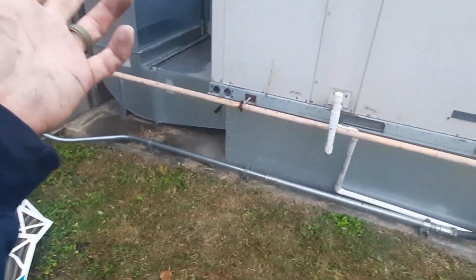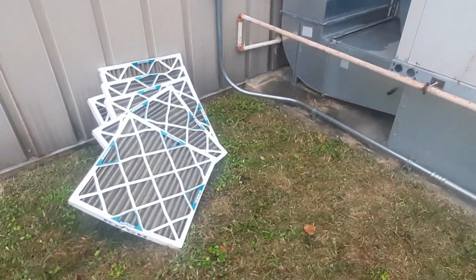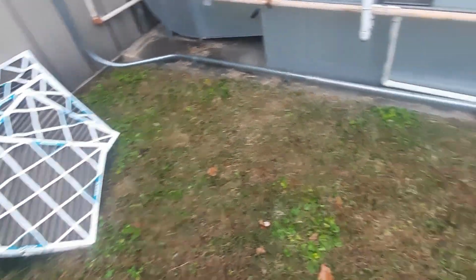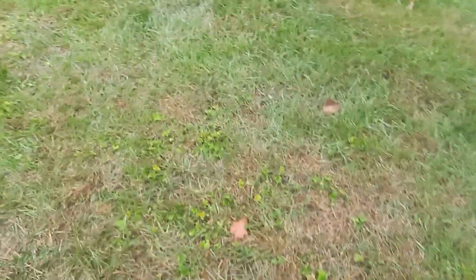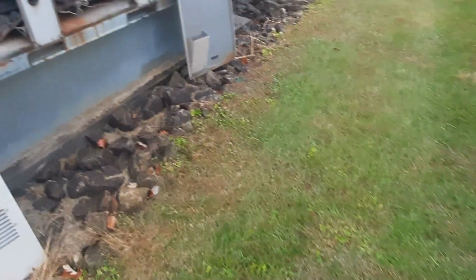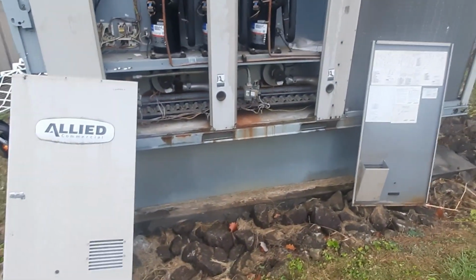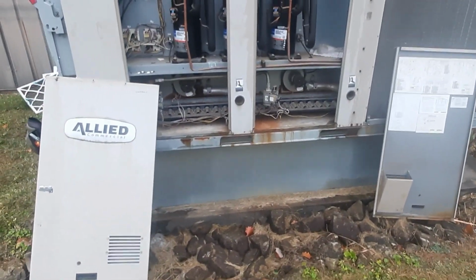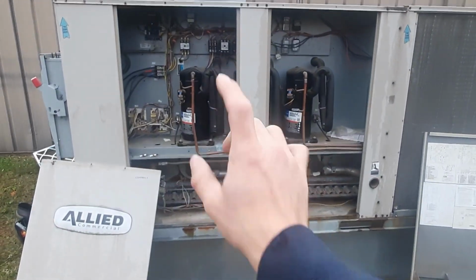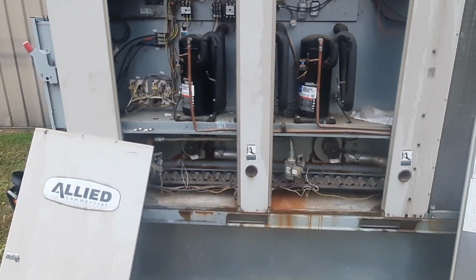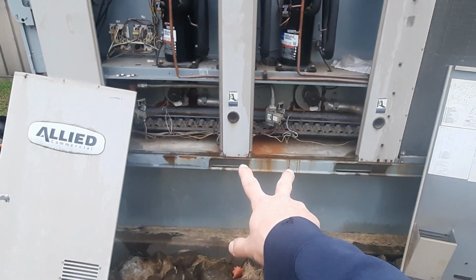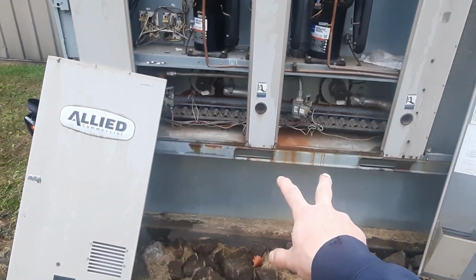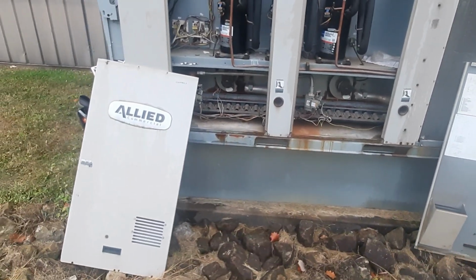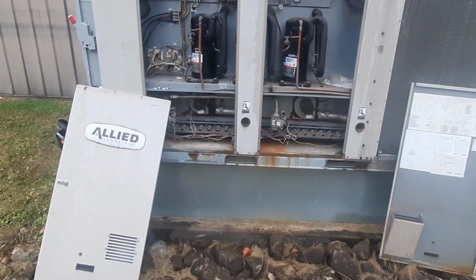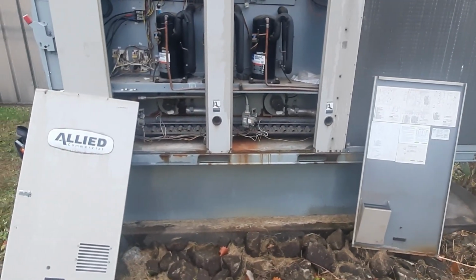Temp rise seems kind of low, but it's 60 degrees coming in. That's our main problem right there. Airflow, airflow, airflow. I had a feeling it was gonna be something simple. This guy just needs a little attention, so I'm gonna save all the burner cleaning and the heat exchanger inspections, and that compressor contactor will probably need to go. The amps were okay on these. We might let them run for a little while and check the amp draw again. That motor there, its bearings are going out, and you can see the rust. So this thing's got a little age to it.